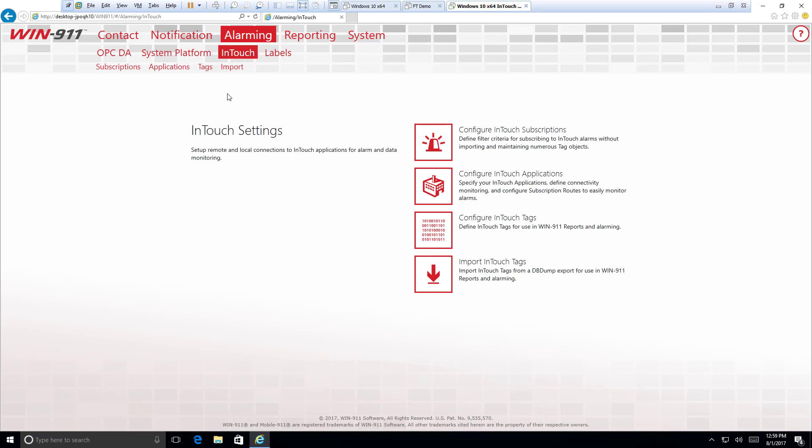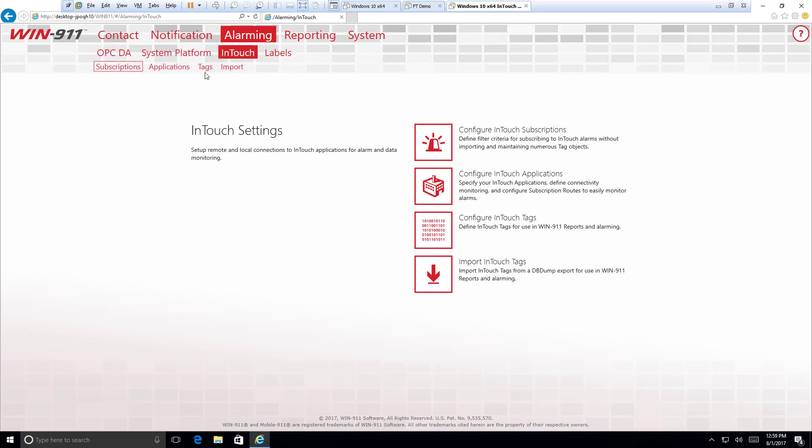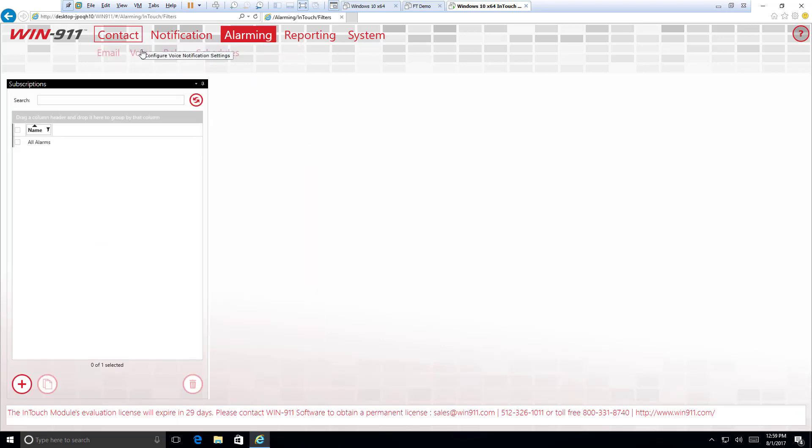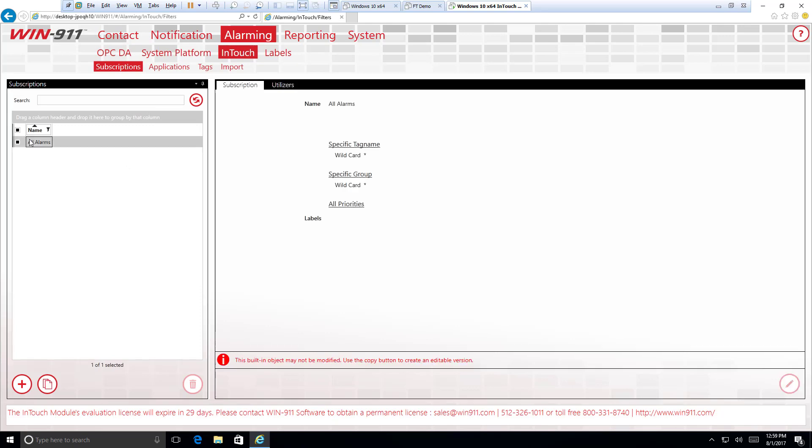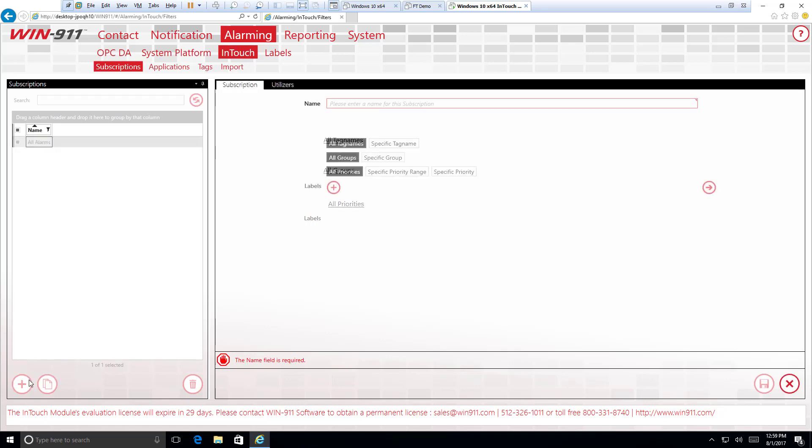Just like with our other tutorial videos, we're going to be doing a left to right sweep of these four tabs right here. Today we have subscriptions, applications, tags, and import. Let's first look at subscriptions which will allow us to filter our incoming alarms and basically ask for which ones you want to pay attention to. You'll notice right off the bat we have a default subscription. This will automatically allow every alarm that InTouch triggers to come through and for Win911 to alarm you based off those.